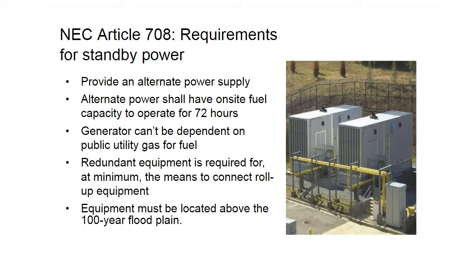Some of the requirements for standby power in Article 708: you need to provide an alternate power supply, so a generator of some sort, or battery systems. The alternate power supply shall have on-site fuel capacity for 72 hours. So basically they do not allow the generator to be dependent on natural gas or some kind of gas fuel. The idea is it has to be completely isolated, independent of any exterior sources. You don't want the gas line to go down and then take down the system. Any standby power has to have redundant equipment at a minimum, or at least a connection for a roll-up piece of equipment. So if you have to do maintenance, you can roll up and bring in another piece of equipment to make sure you have standby power supply during that maintenance time.